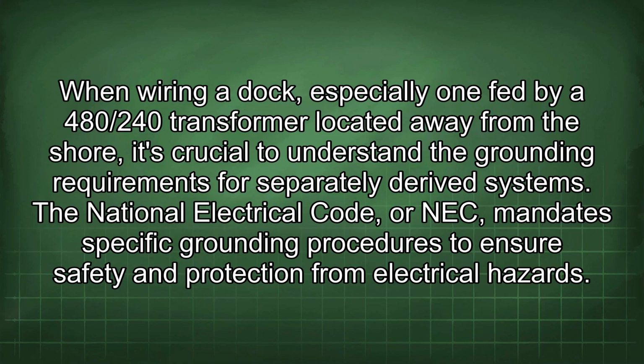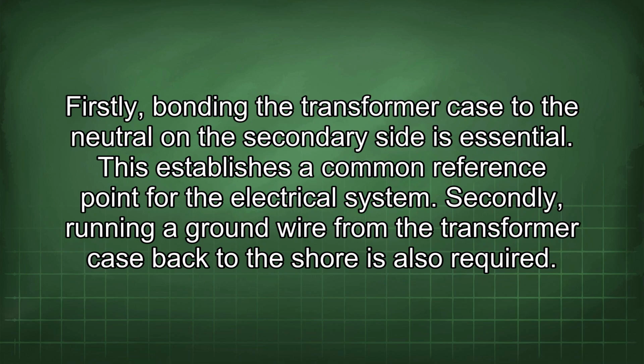Wiring a dock, especially one fed by a 480/240 transformer located away from the shore, it's crucial to understand the grounding requirements for separately derived systems. The National Electrical Code, or NEC, mandates specific grounding procedures to ensure safety and protection from electrical hazards. Firstly, bonding the transformer case to the neutral on the secondary side is essential. This establishes a common reference point for the electrical system. Secondly, running a ground wire from the transformer case back to the shore is also required.